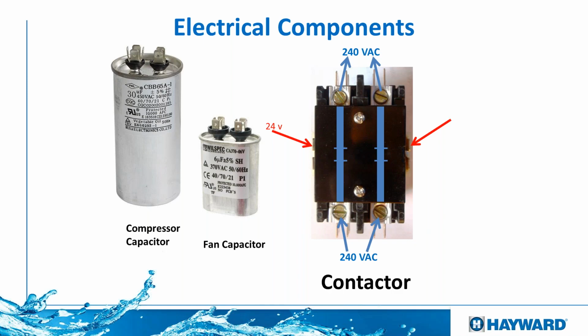Every single one of the capacitors has a number of UF, which is what it's rated for. Now for the compressor, it's not going to be 30, it will be something like 80. So when we check the capacitor, we need to make sure that we have close to 80. If it reads nothing, then we know it's definitely bad. Another way to see it is if the capacitor is blown up, like inflated, then we know that it's also bad.